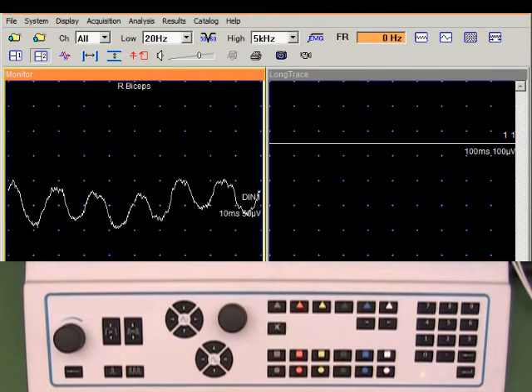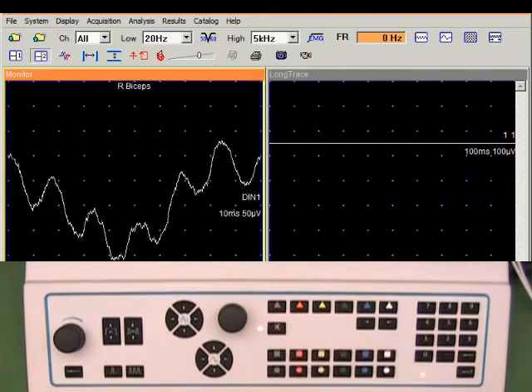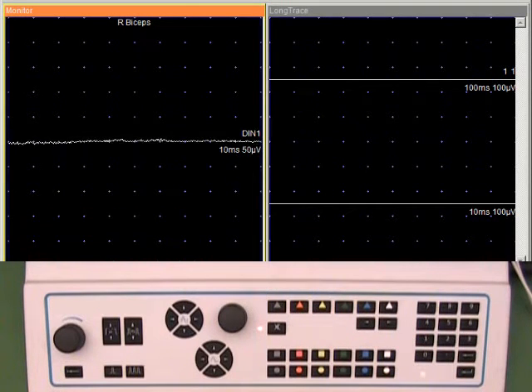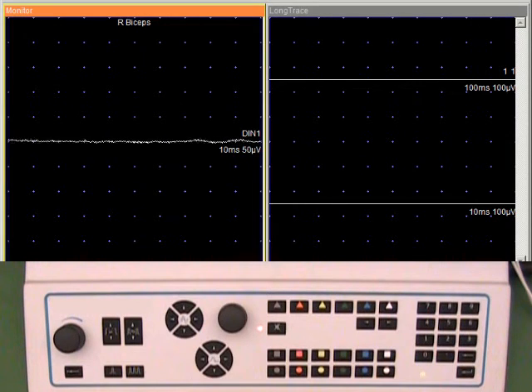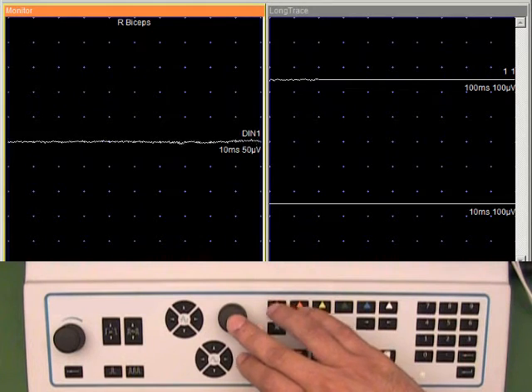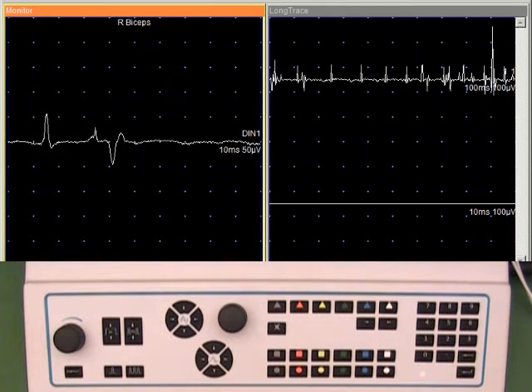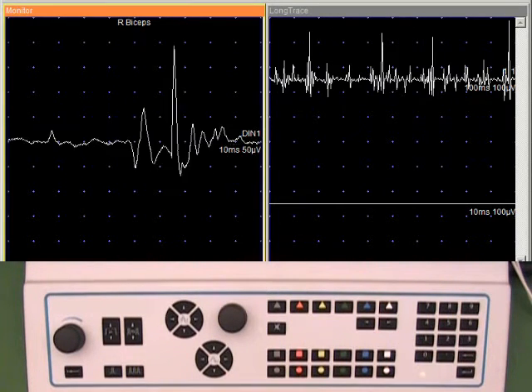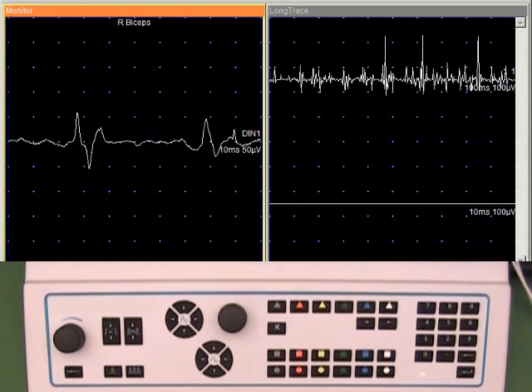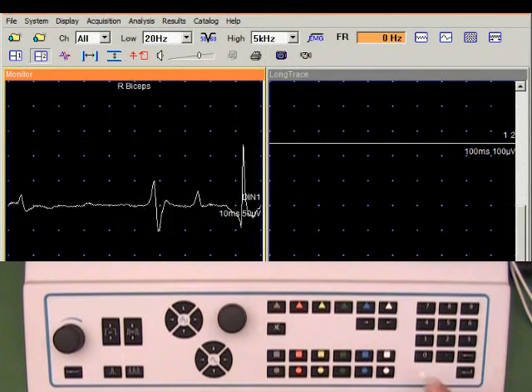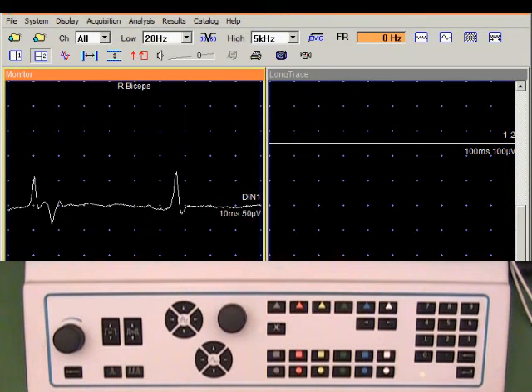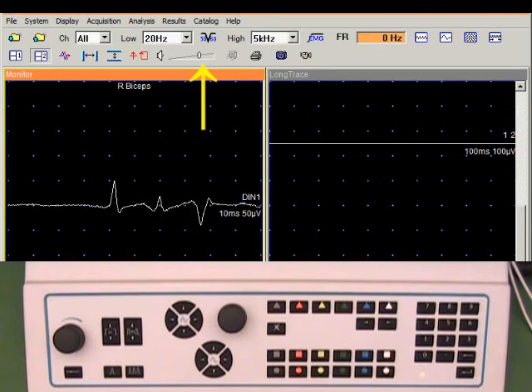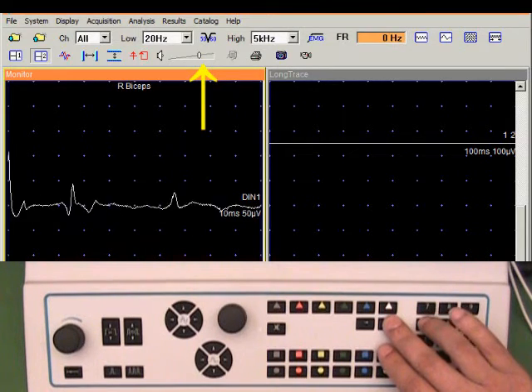We can enable the audio at any time by unmuting it. We can now hear the sound of EMG and mute it. We have a very nice baseline. We can activate the audio and start data collection by pushing the select knob. Now we have the sound and we can see the sharp crisp EMG activity. The volume levels can be adjusted using the two arrow keys. This control is shown at the top in the toolbar. I'm going to increase the audio.